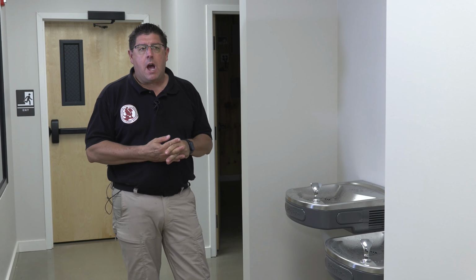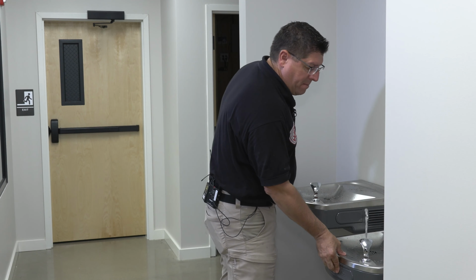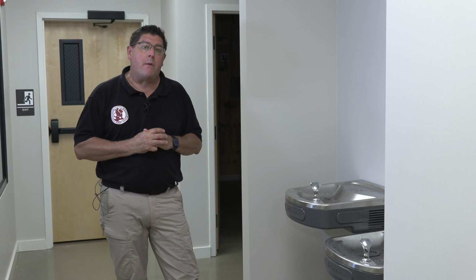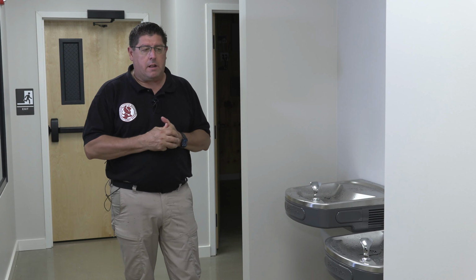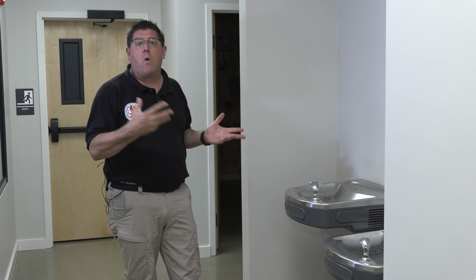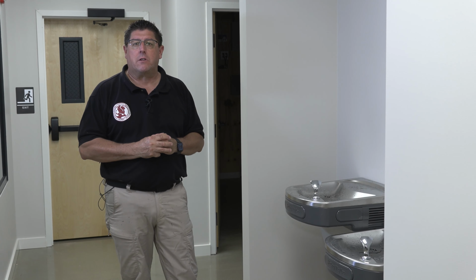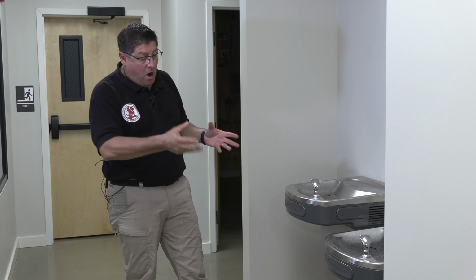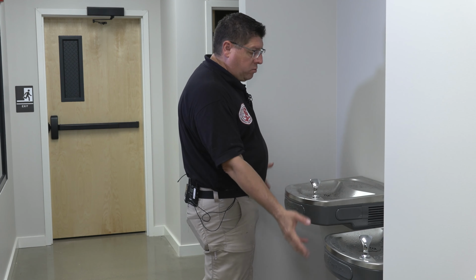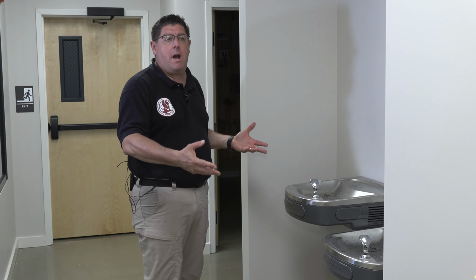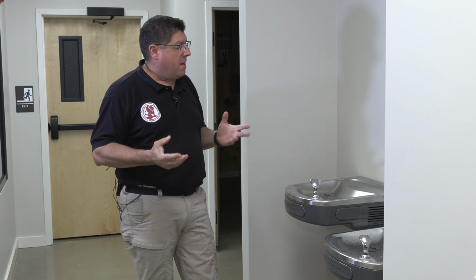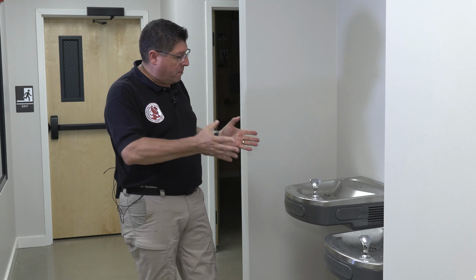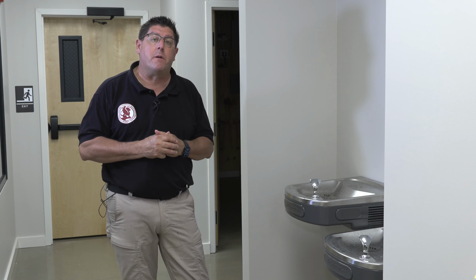So in many cases, I will operate the water fountain as part of the plumbing, but I will usually add a comment into my report that describes these and a description that talks about Legionnaire's disease. And there are other ways now you can distribute drinking water to your employees and your clients that doesn't involve a water fountain. And if you are going to use a water fountain, again, these ones that are super chill, they're great, but they have to be used. If you have one that doesn't chill, but maybe it's just a dispenser, maybe it's a water fountain that comes from the tap that fills a portable water bottle, then those are a different animal. But we do have to make sure that we look at water fountains as part of the plumbing inspection.